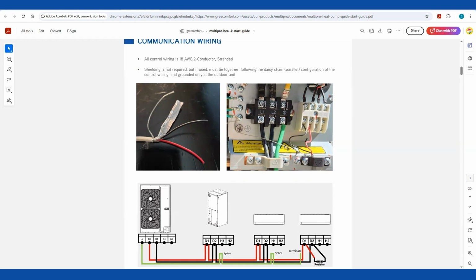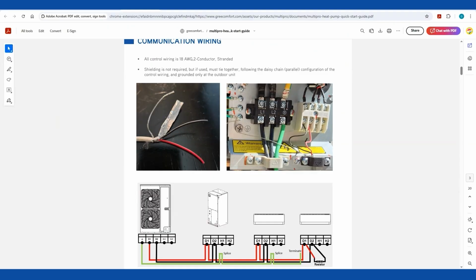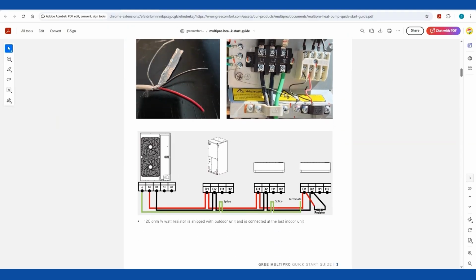We show you a picture of a grounded shielded wire here because that's what grounded shielded wire looks like. We don't require you to have grounded shielded cable. But if you run grounded shielded cable, you would absolutely want to go ahead and hook it up. There's no reason for you not to if you already got it. Just keep in mind when you're doing grounded shielded wiring, it has to be done properly. So you only ground it outside. And then inside, you're going to splice this.